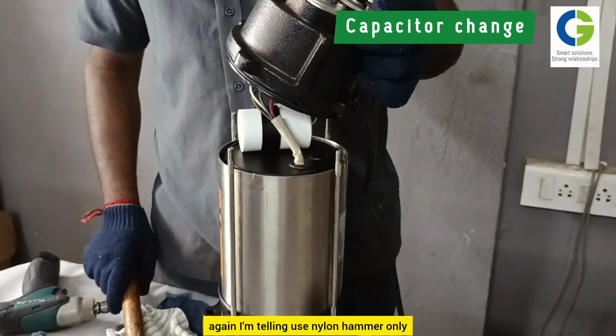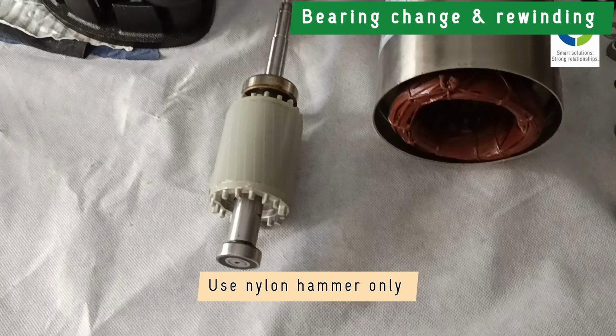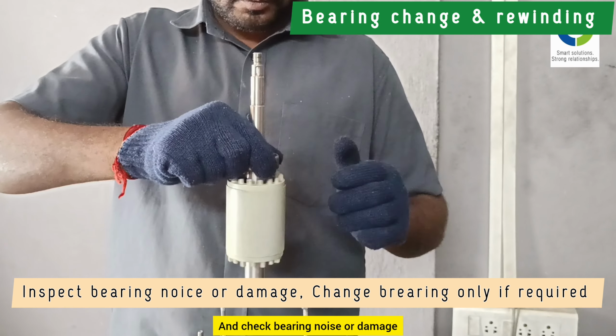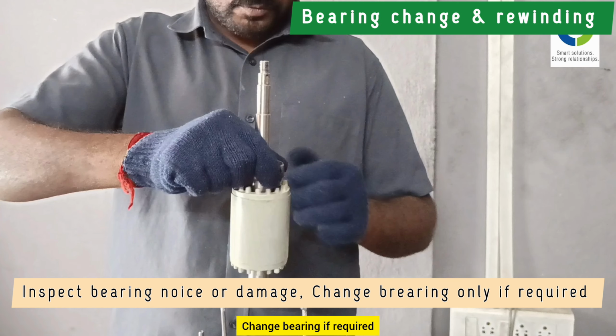Remove the top bearing cover using a lengthy bolt. Whenever you tighten the bolt, the wound stator will come out. No need to hammer. Clean the wound stator. Now we can see here the rotor with shaft. We have provided two bearings here. These are the parts used in this pump. Check for bearing noise or damage. Change the bearing if required.